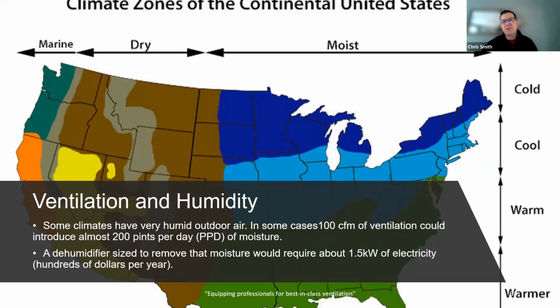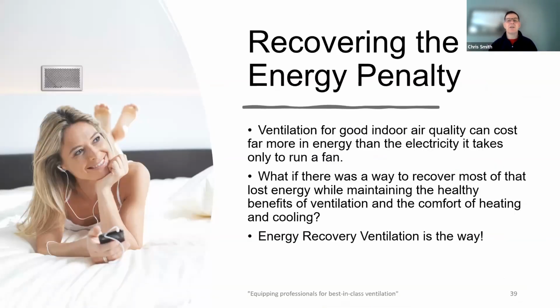If we talk about humidity, there's even more impact. In many portions of North America, there's a lot of humidity during much or most of the year. And in some cases, 100 CFM of ventilation could introduce almost 200 pints per day of moisture into the building. So you could be looking at another 1.5 kilowatts of electricity just to run the dehumidifier to deal with that ventilation, if all you're doing is some sort of exhaust-only ventilation. So balanced ventilation with heat recovery is a solution. We want good indoor air quality, so we want to ventilate. We recognize that ventilation can cost a lot of money. Besides just the fan energy, it costs in conditioning energy. So we want to be able to recover that, and we can do that with energy recovery ventilation.